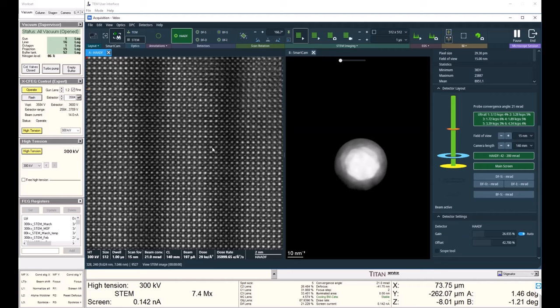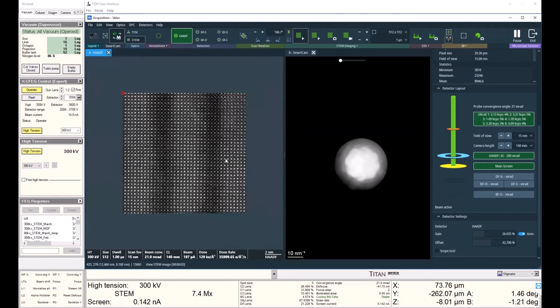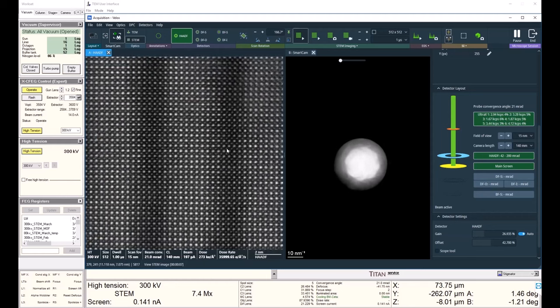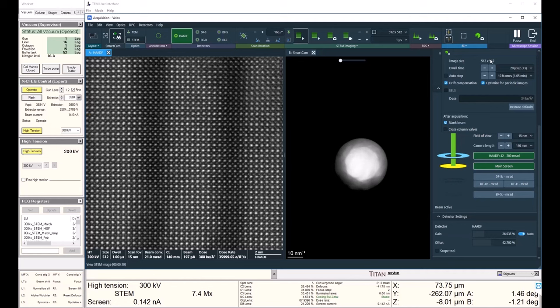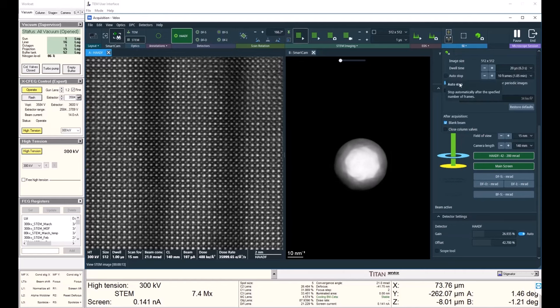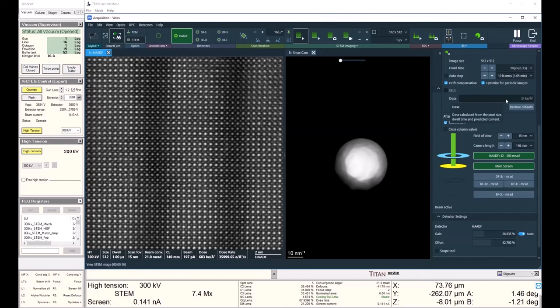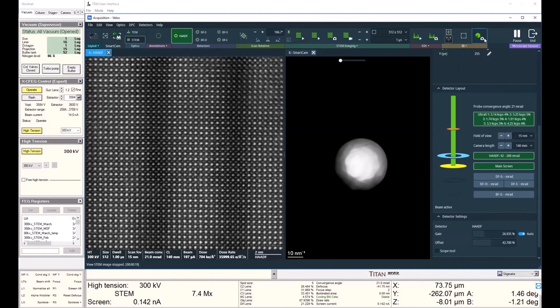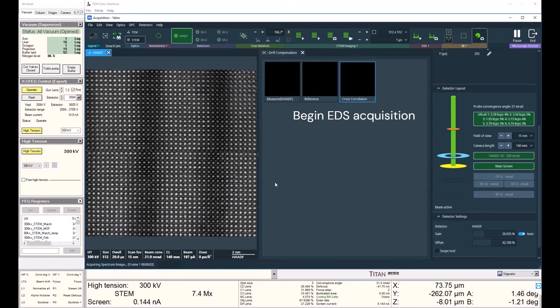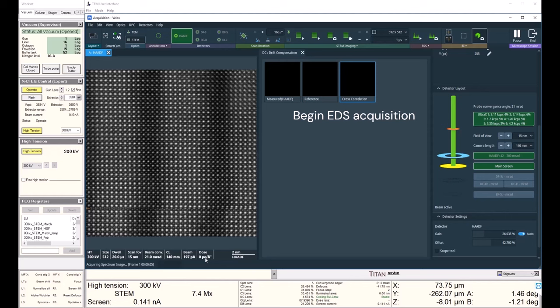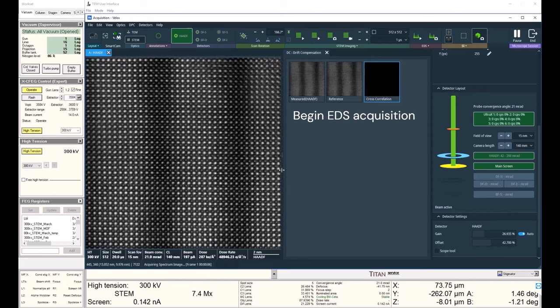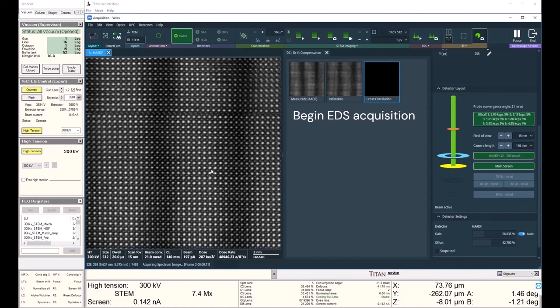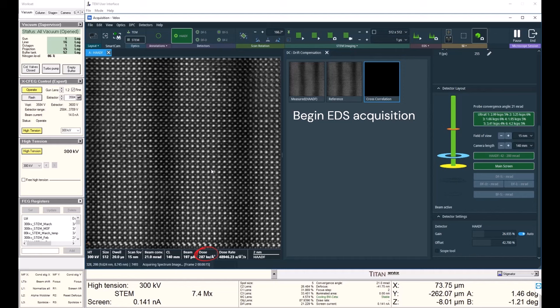I like this area, so I'm going to go ahead and just move my beam to a parked position outside the frame and check my spectrum image settings. So I'm going to use 20 microsecond dwell, drift compensation optimized for periodic images, and I can see what my dose per frame will be. As I acquire each frame, I will see the dose increase, and that will be summed through all the frames. Now my dose has gone up again.